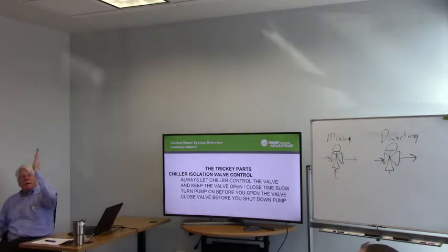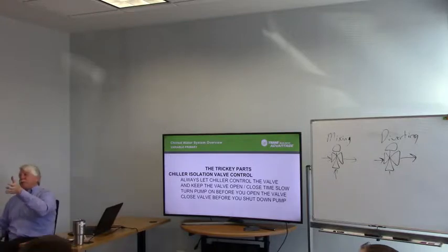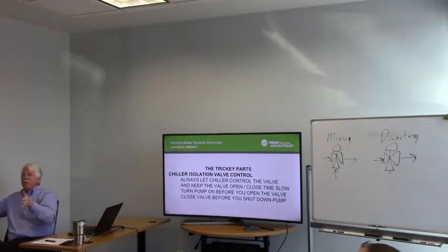This chiller is running and the VFD is at 80% speed. When we turn on a second pump, what speed do we normally turn it on at? 20%. Well, but as soon as it's ready to run, we match pump speeds. You always run your pumps at the same speed. So that pump is going to go up to 80% as soon as we start it. And the good news is, that's what we want.